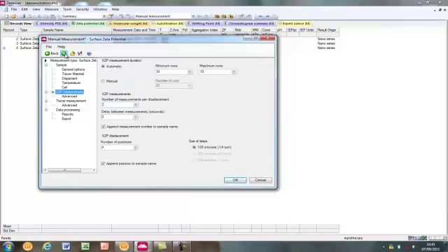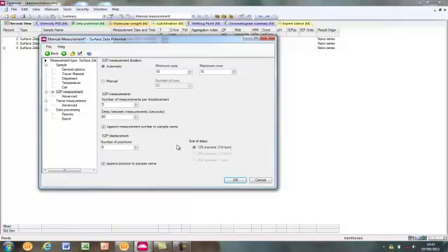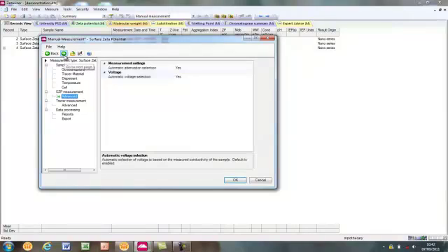The surface zeta potential measurement branch allows settings specific to this measurement type to be set. The maximum number of subruns per measurement should be left on automatic. Since these measurements are slow field measurements only, it is recommended not to exceed the default 15 subruns as this could unduly heat the sample. It is recommended to run five measurements at each of five different displacements to increase the certainty of the data. It is also recommended to insert a wait of 60 seconds between each measurement to ensure the sample is re-equilibrated before moving on. The advanced settings can be left to automatic.